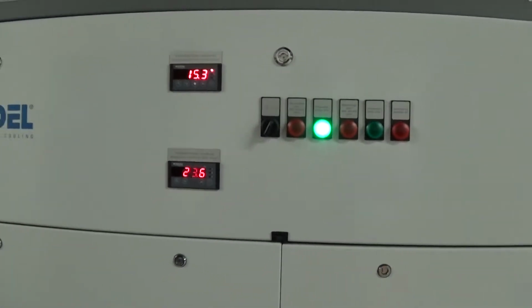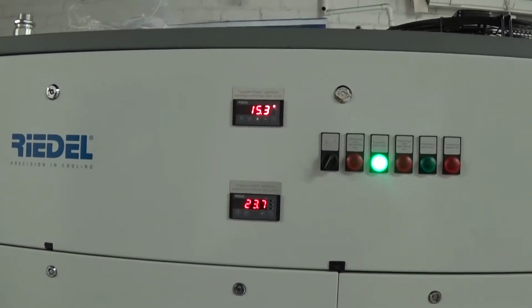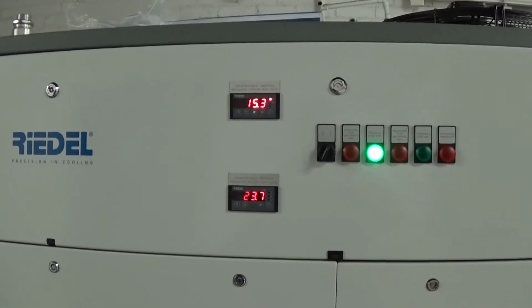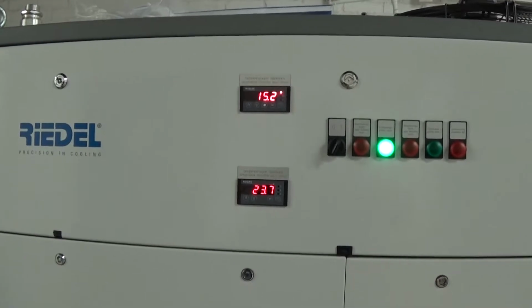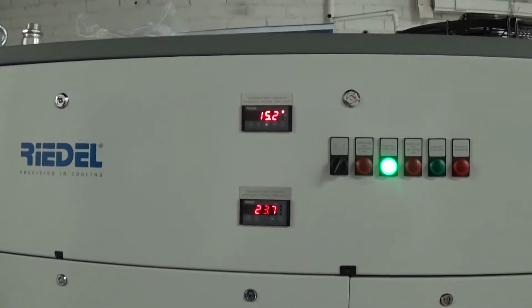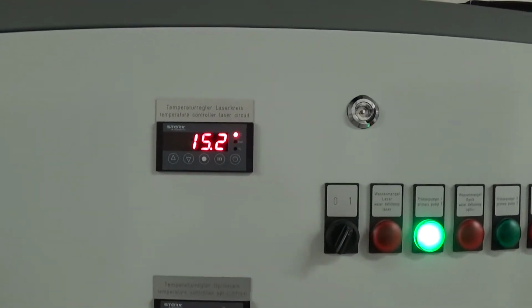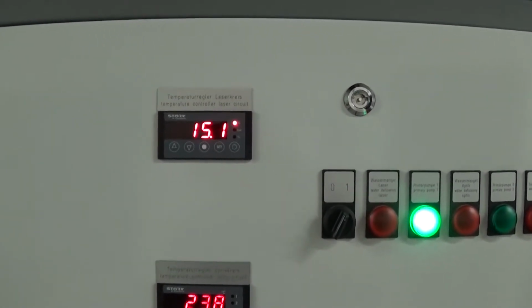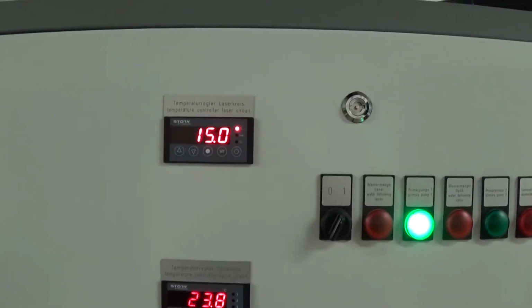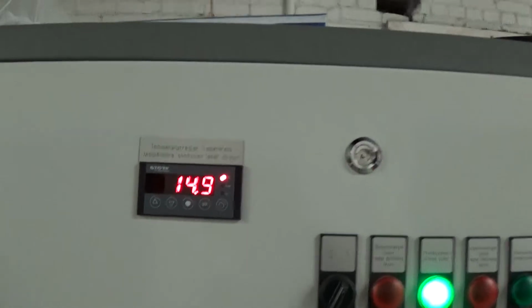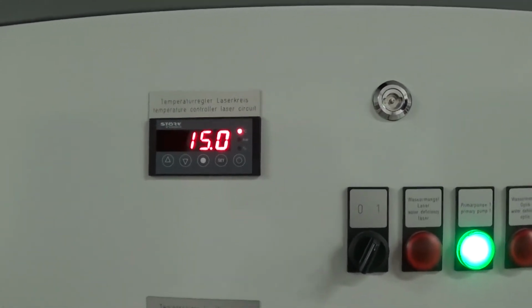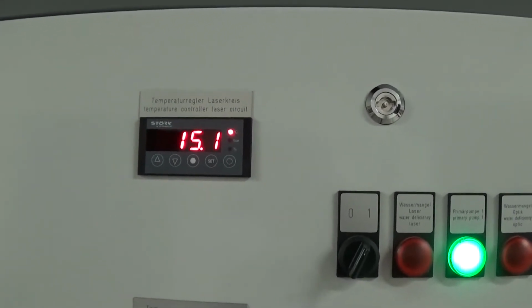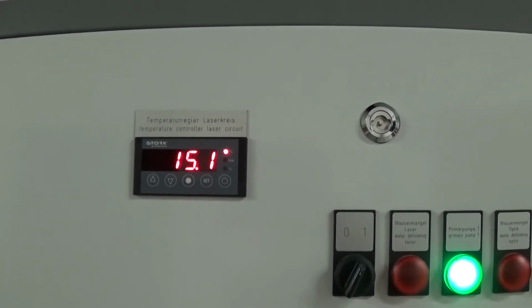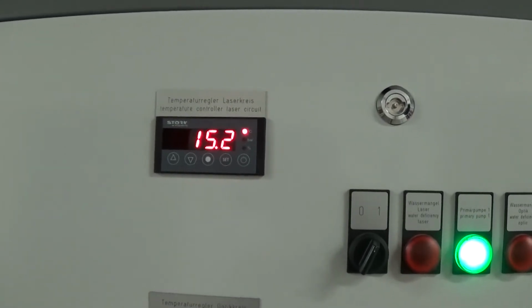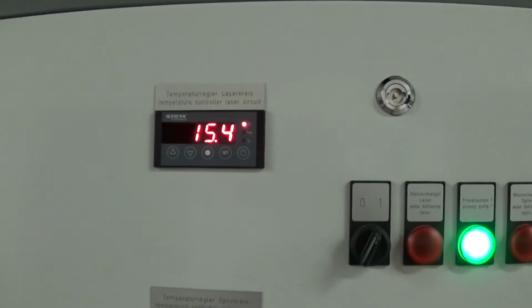And with our minimal load we have here, this is probably just going to stabilize right at that 15 or 14 C and change, and just hold that temperature. Yeah, the hot gas just went off a little bit. If it turns back on, you'll hear that hissing. So now it's coming back on. And again, we have a little bit of a load inside the tank. The fans have been satisfied by the pressure, so the fans are shut off. We still have one compressor running here with the hot gas on. So right now I could be here all day just because the chiller is finding a way to maintain that temperature between the compressor running, fan going off, and the hot gas.